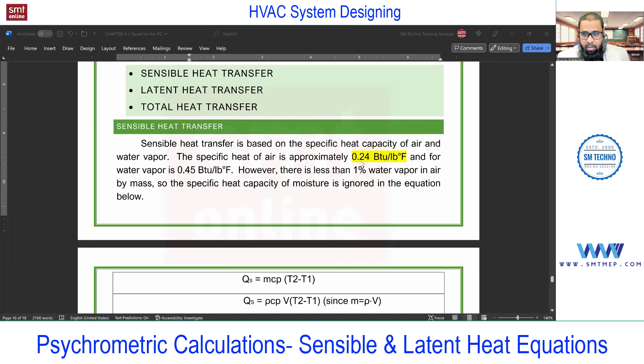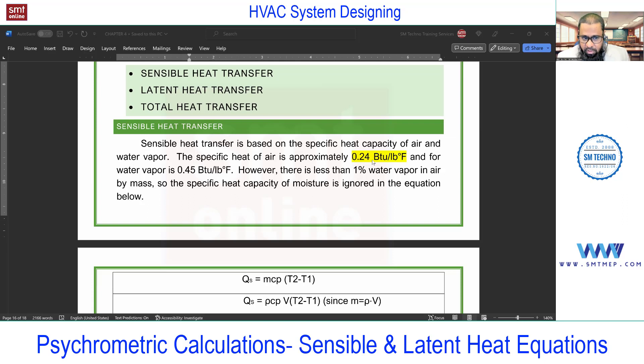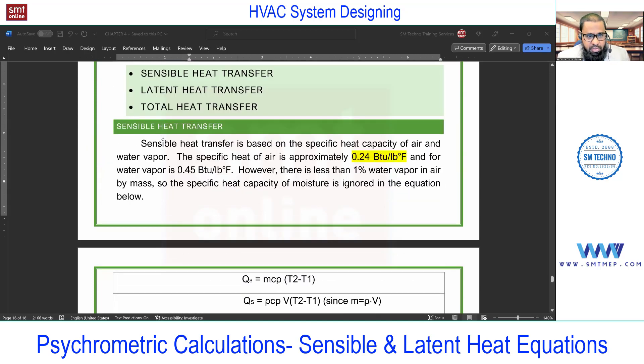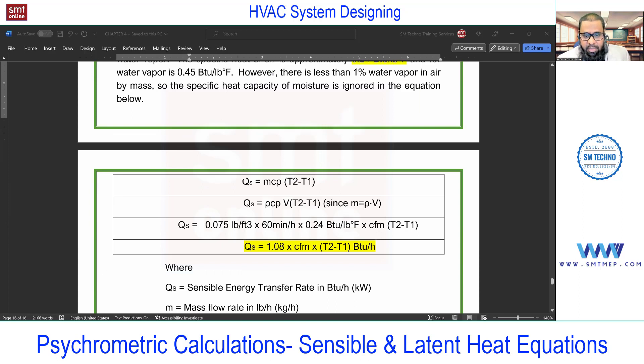The specific heat of air is 0.24 BTU per pound per degree Fahrenheit. Remember, at the time of learning BTU in Chapter 3, we discussed specific heat of water — in the English system it is 1.0, meaning one BTU is required to raise one pound of water by one degree Fahrenheit. Similarly, for air it is 0.24 BTU per pound per degree Fahrenheit. We also have a specific heat for vapor of 0.45, but the quantity of vapor compared to total air is very small so we are not considering that value.